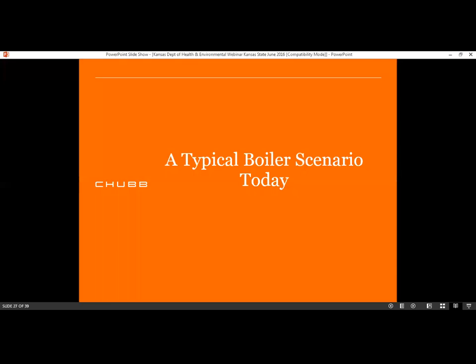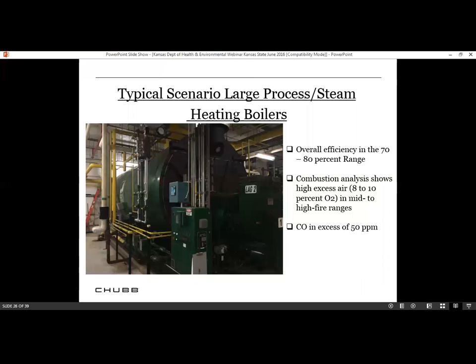A typical boiler scenario today, this is a boiler that is at North Kansas City Hospital, and we're currently, right now, to this day, doing an upgrade. The burner on there, the overall efficiency was in the 70 to 80% range. The combustion analysis showed high excess air. CO was in excess of 50 parts per million. We were upgrading the burner system here.